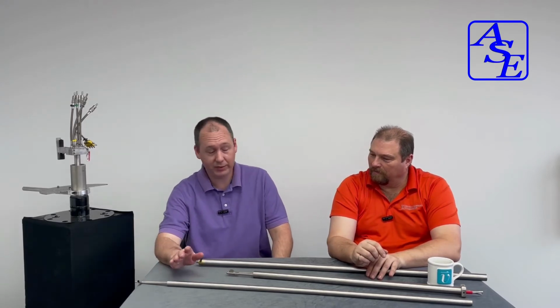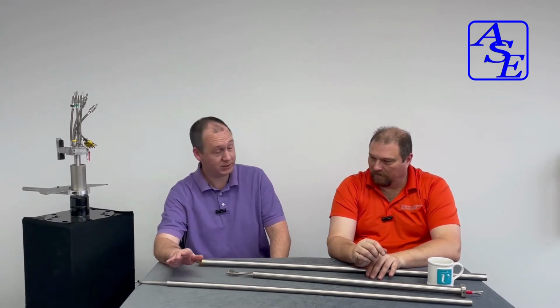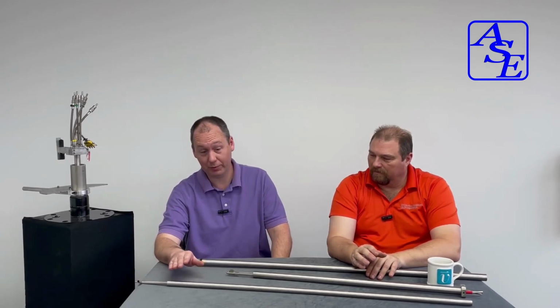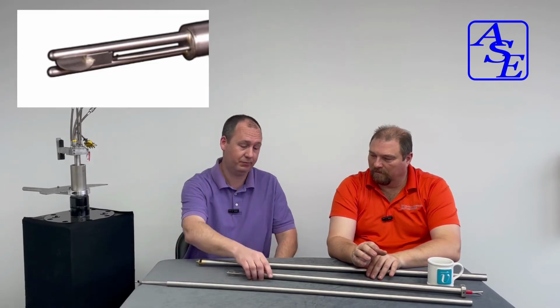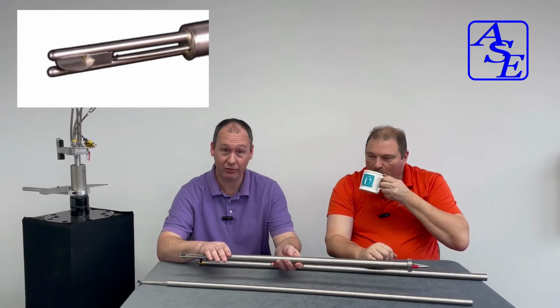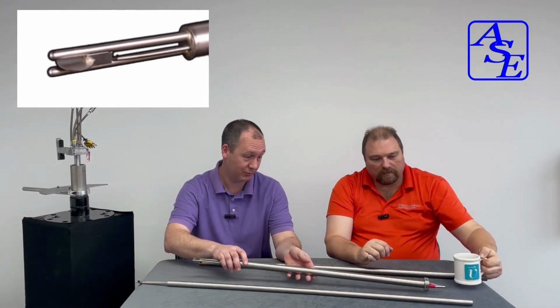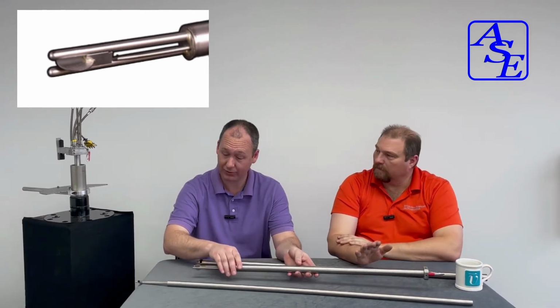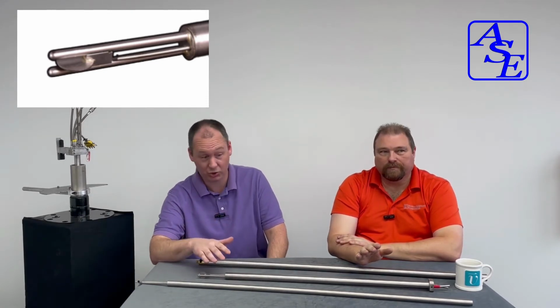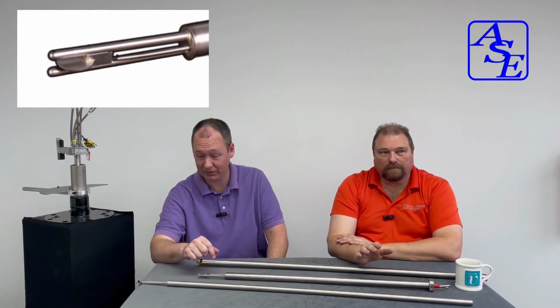So like I say, primarily these are used for coal pipe testing. This is used for measuring the coal in a pulverized coal power plant. You measure the coal through each individual pipe. So you'd use this dirty air probe, and you just use this to measure the velocity and the temperature. So this is the velocity and the temperature of the air, not the coal typically, but this is what's used for setting your extraction rate when you move on to the extractive testing.